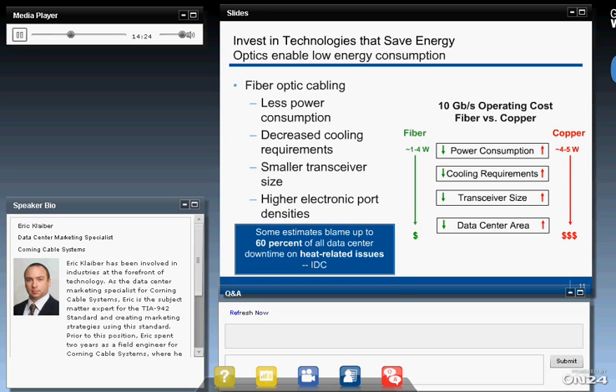The transceiver on the copper side is typically larger than a fiber transceiver, so we have fewer ports per blade, meaning we need more switches and more data center area. The larger your data center area, the larger the CRAC units you need to cool it and push enough air volume through to avoid hot spots. On the fiber side, even though there's optical loss, it doesn't generate heat—it's all done through light, and light is the only thing lost. The transceiver is small, leading to higher densities and lower data center area for the same amount of information passed through.